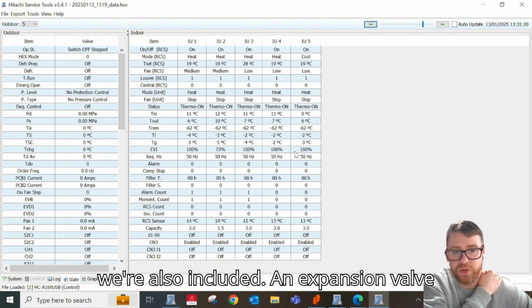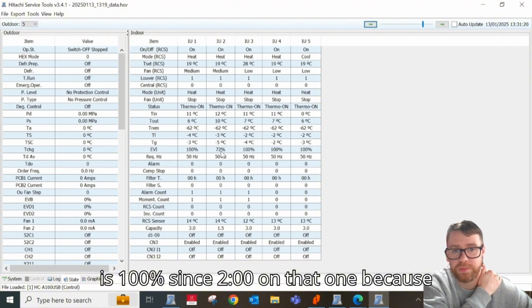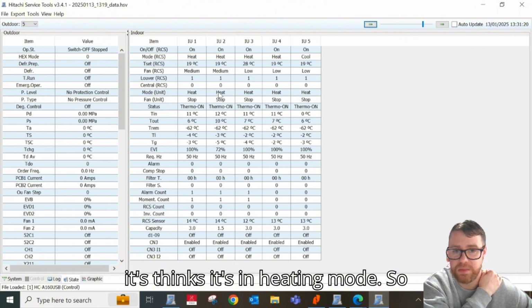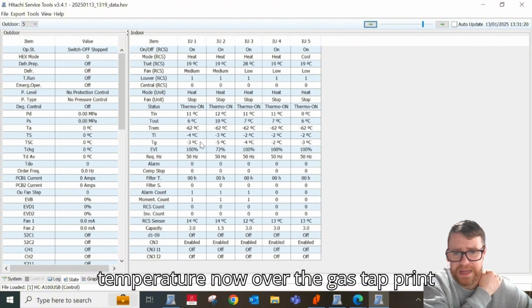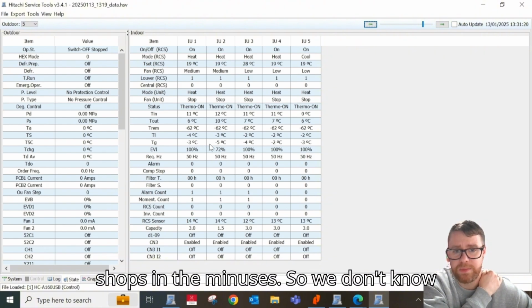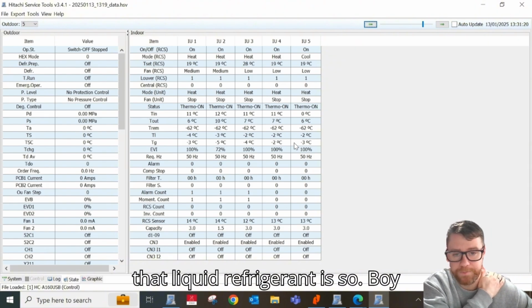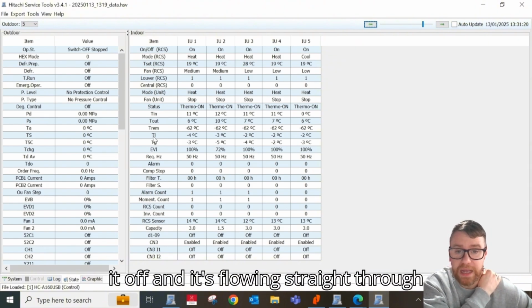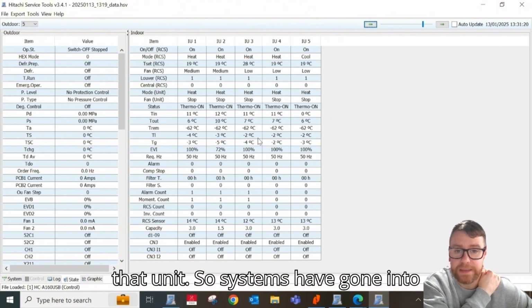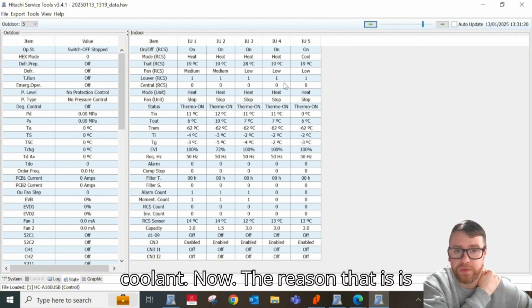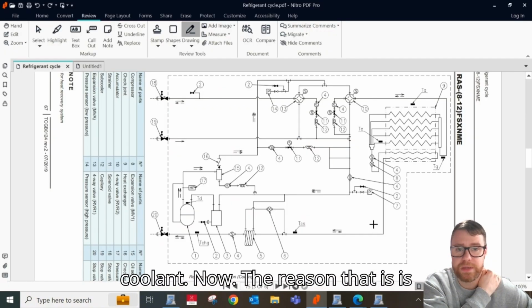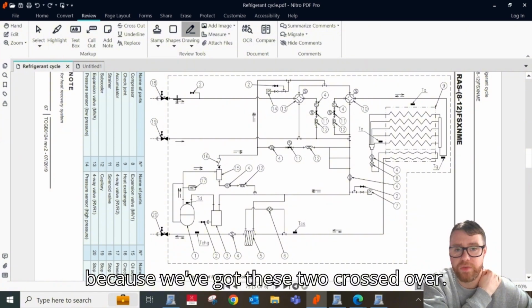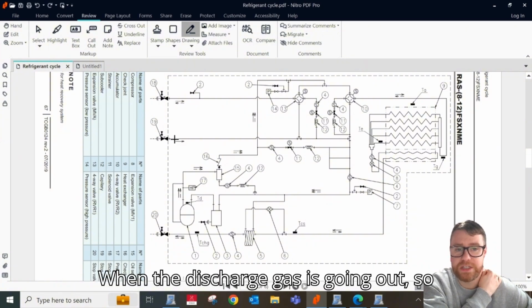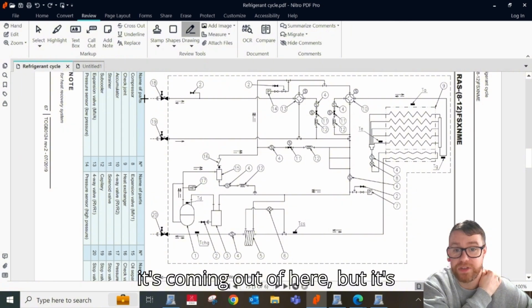Now the expansion valve is 100%, 72 on that one, because it thinks it's in heating mode, so it's an open expansion valve. Our liquid temperature is there, and we've got the gas temperature in the minuses, so we know that liquid refrigerant is boiling off and flowing straight through that unit. So the system has gone into cooling. The reason is that we've got these two crossed over. When the discharge gas is going out, it's coming out of here, but it's actually going into the suction.